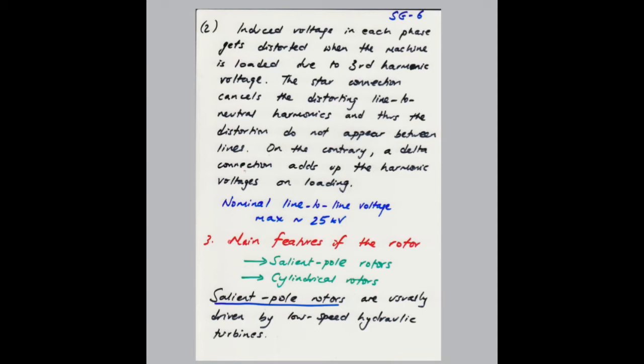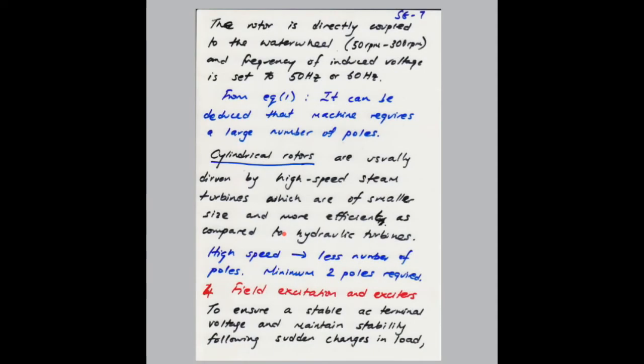The second feature that we're going to look at is the rotor of the machine. So there are two types of rotor. You have what we call salient pole rotors, right, which are normally used for hydraulic turbines. They are normally low speed. And the second type is your cylindrical rotors. Now for the machines that are hydraulic, their speed normally lies between 50 RPM to 300 RPM, and obviously the frequency is set as either 50 Hertz, like we use in South Africa, or 60 Hertz that they use in America.